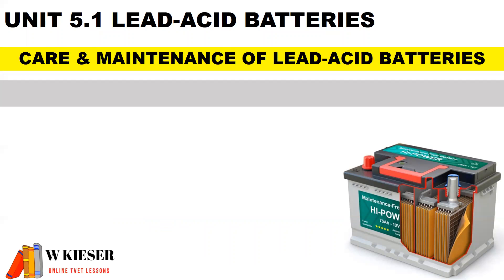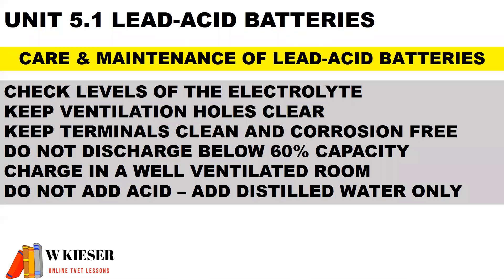For the care and maintenance of lead acid batteries: check levels of the electrolyte, keep ventilation holes clear, keep terminals clean and corrosion free, do not discharge below 60 percent capacity, charge in a well ventilated room, and do not add acid — rather add distilled water only.